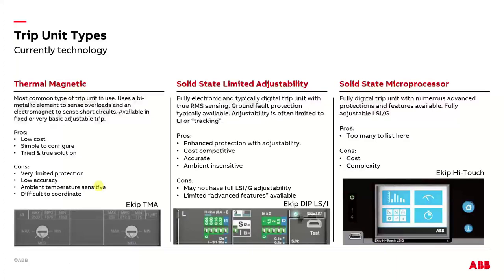So the accuracy is just not very good. But usually, what it's protecting in terms of cables and transformers, they're also sensitive to the ambient, so they kind of match up. So in the early days of electrical loads, when your breaker was just protecting a cable or a transformer or a panel board, these were fine. And they still are in most cases. They're difficult to coordinate. And we'll get more into that.